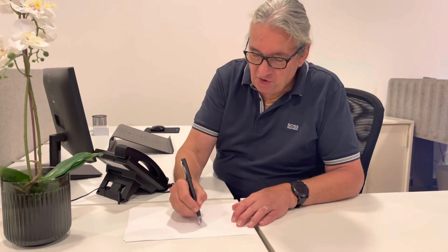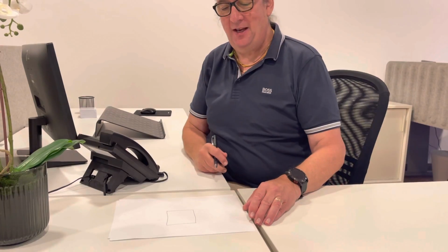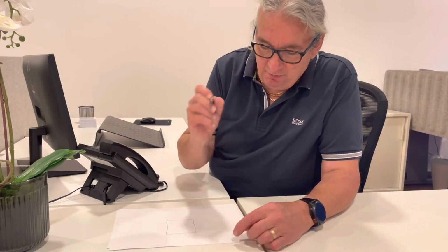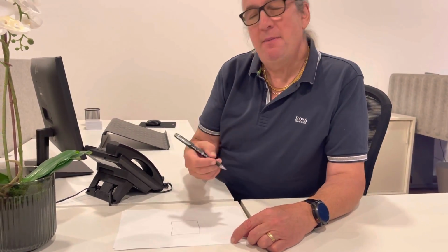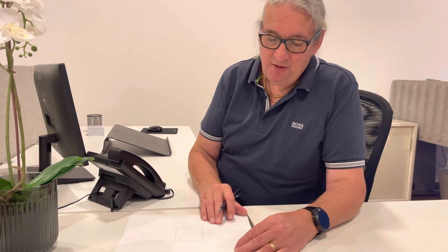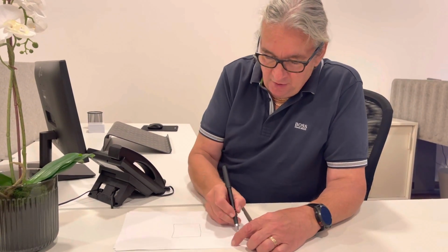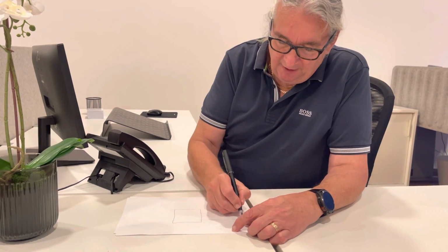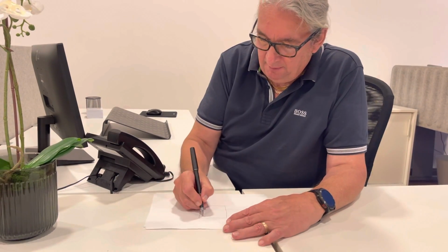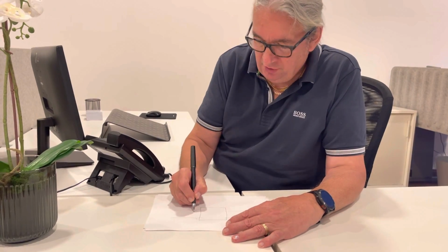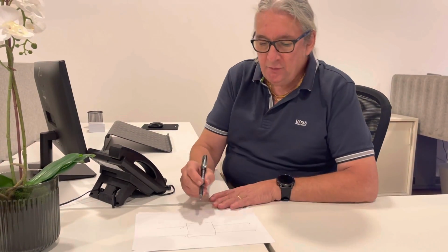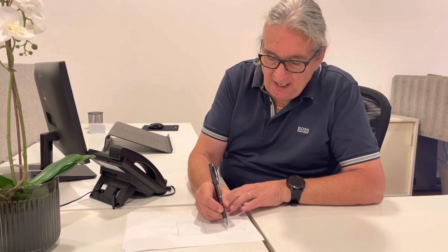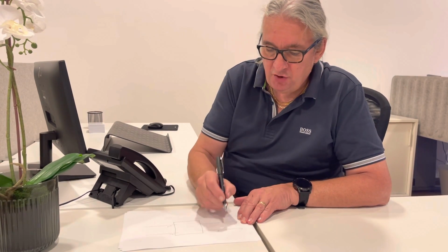How does an RCD work? So basically, an RCD is a device that your power goes into. I'll draw the RCD as a box, simple like that, okay? There used to be a Wheatstone bridge, now they're very simple with microchips, most of them using these little Fairchild chips or whatever. So basically on the bridge here, I have my live and neutral in, and I have my live and neutral out.